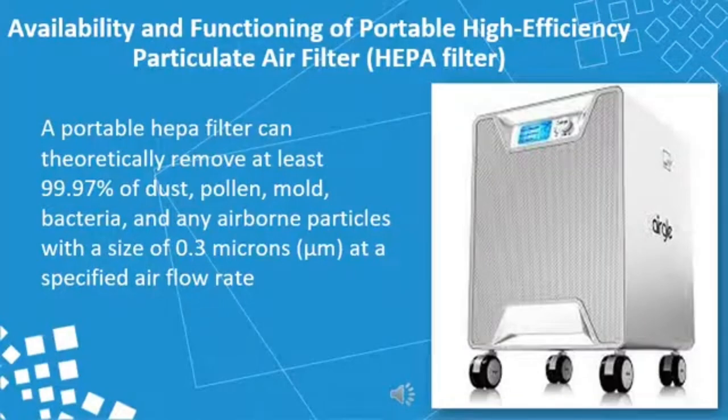The second substandard required for this aspect is the availability and functioning of portable high efficiency particulate air filter, or HEPA filter. A portable HEPA filter can theoretically remove at least 99.97% of dust, pollen, mold, bacteria, and any airborne particles with a size of 0.3 microns at a specified airflow rate.